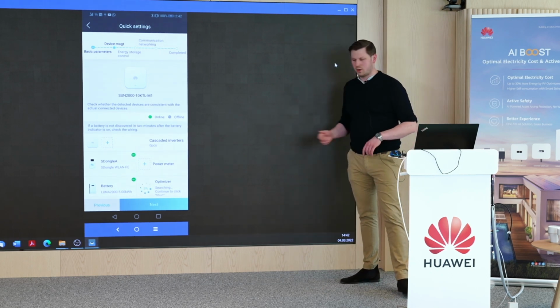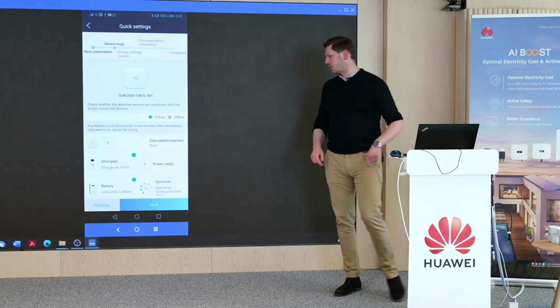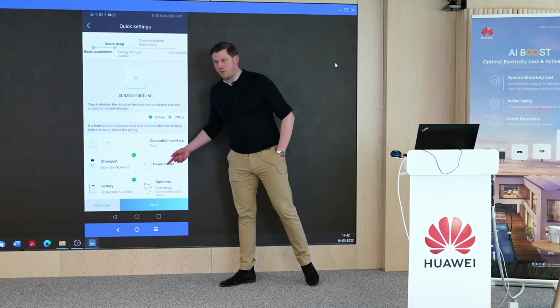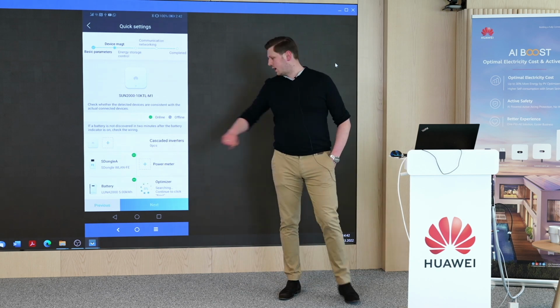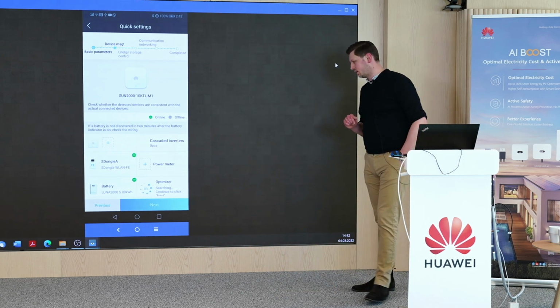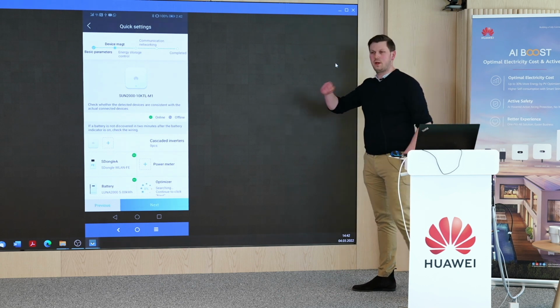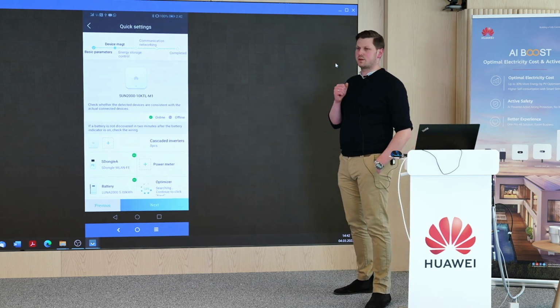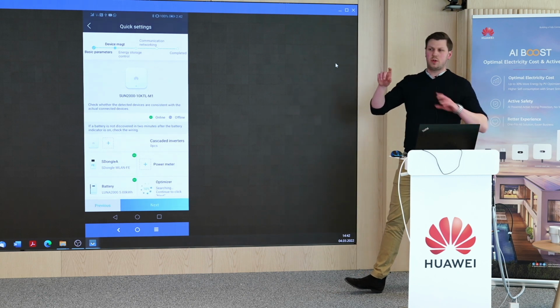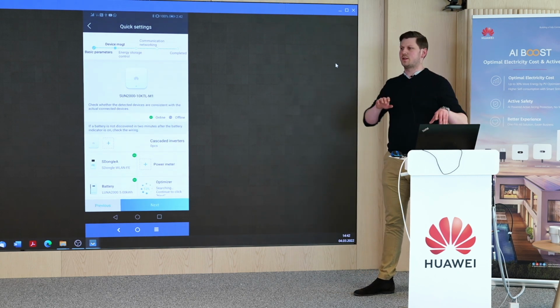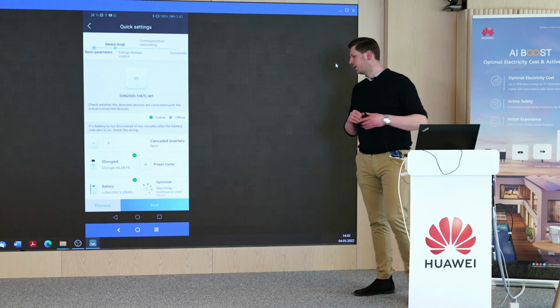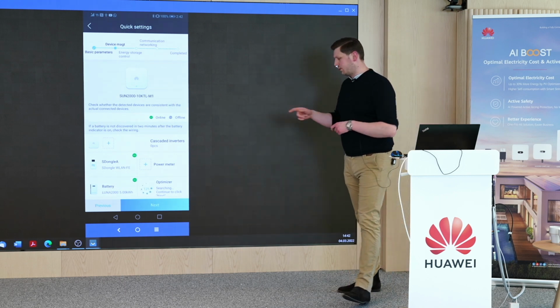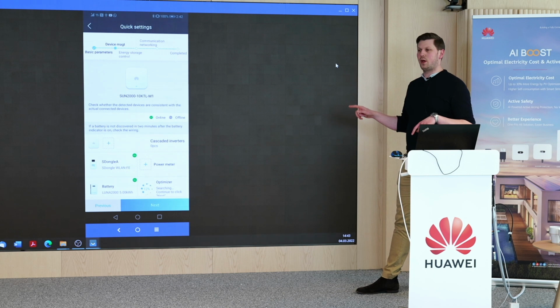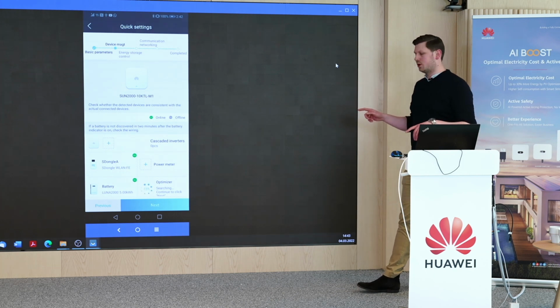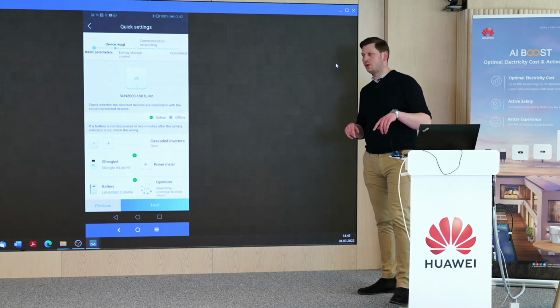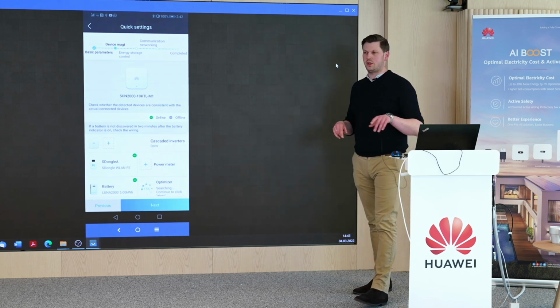This is the part where you cascade your inverters, for example adding some power meter and detecting all devices connected to the system. Right now the system is looking for optimizers. The communication with the optimizers is by power lines, by M-bus, not wireless connection. So if you have, for example, the fully optimized system, you might find some prompt telling you your input voltage is 0 volts.